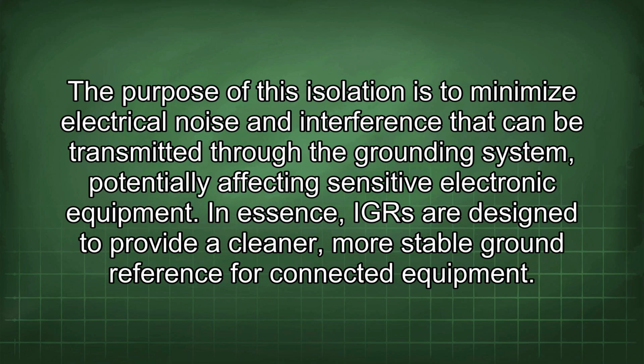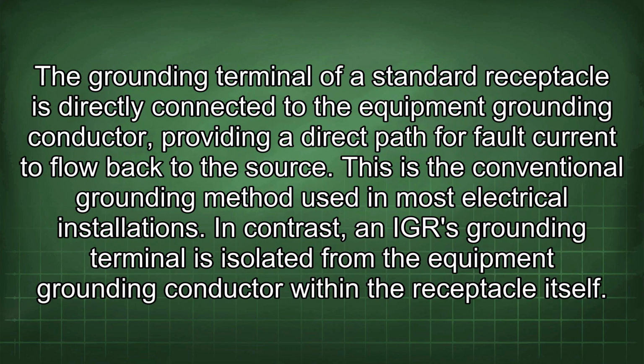The purpose of this isolation is to minimize electrical noise and interference that can be transmitted through the grounding system, potentially affecting sensitive electronic equipment. In essence, IGR are designed to provide a cleaner, more stable ground reference for connected equipment. The grounding terminal of a standard receptacle is directly connected to the equipment grounding conductor, providing a direct path for fault current to flow back to the source. This is the conventional grounding method used in most electrical installations.